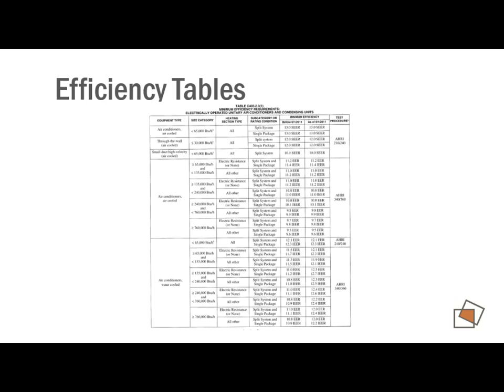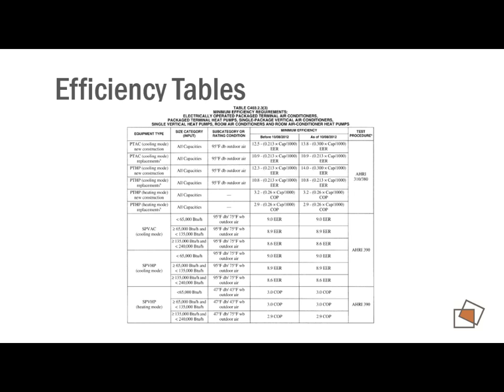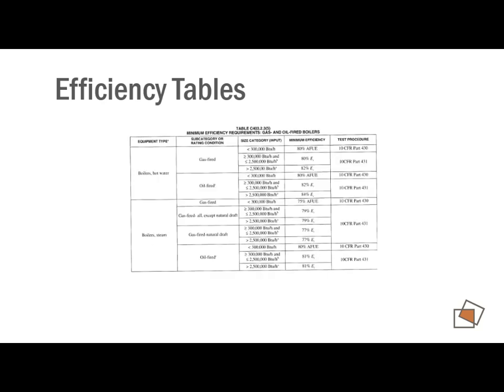I've got a couple, but here's your air conditioner up at the top. I doubt you can read that number, but that's your less than 5 ton units. 13 SEER is what it's saying the efficiency has to be. This table here has PTAC on it, so if you're doing a hotel or something with PTACs, then it's saying these have to meet a certain EER rating. And then this one here is boilers. So here's your gas-fired boilers. If you're above a certain BTU rating, then you have to hit 80% efficiency or whatever it calls out here.